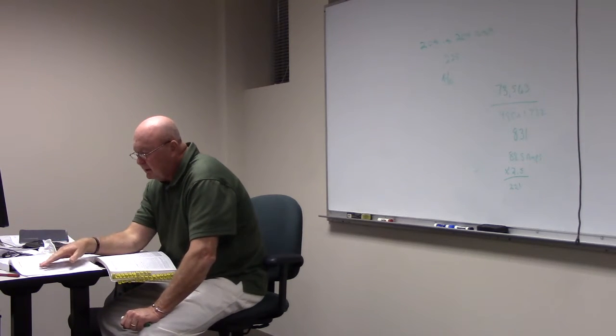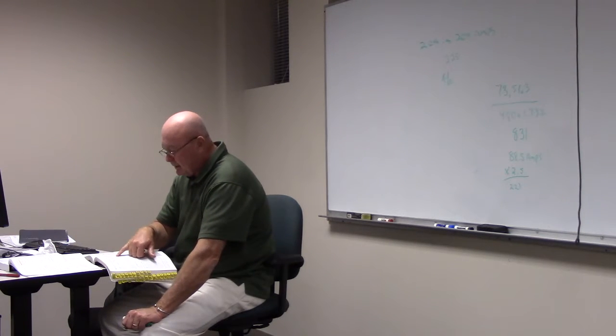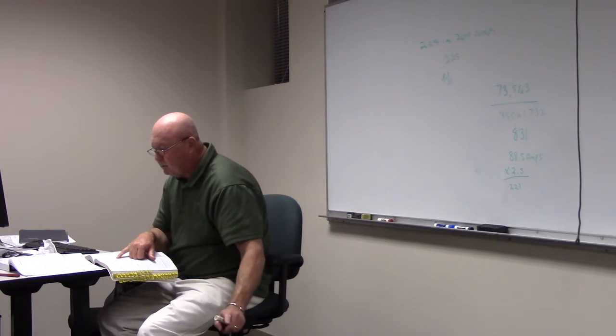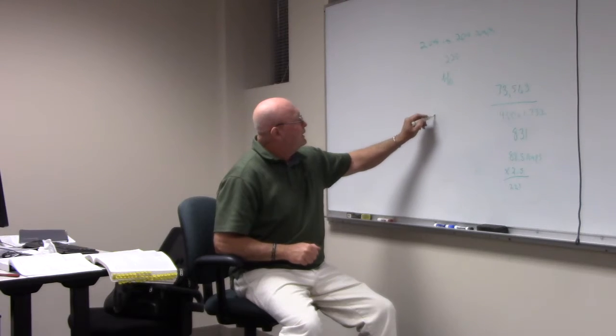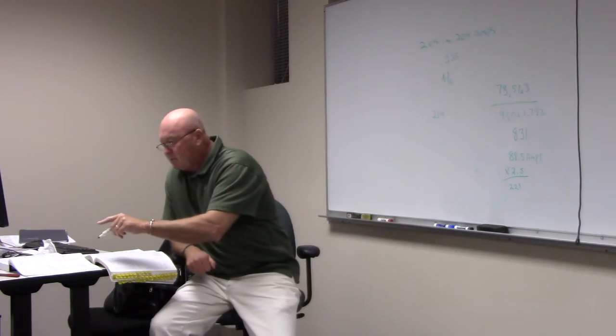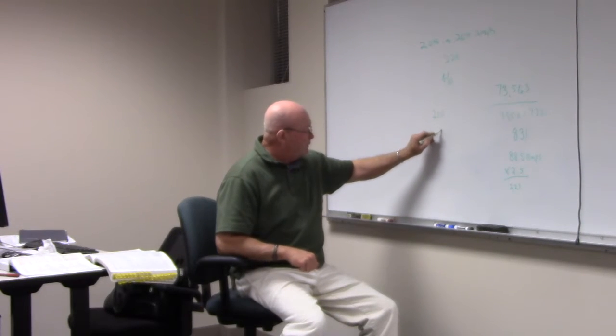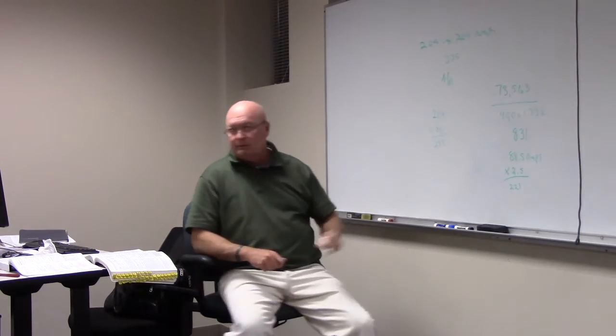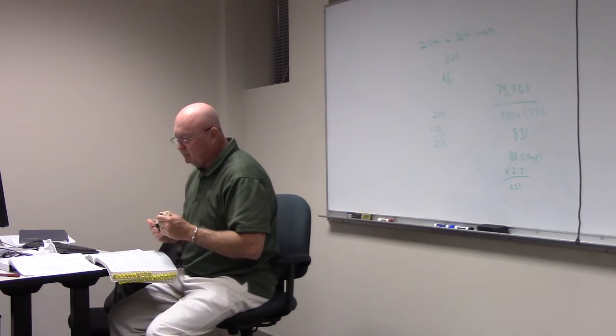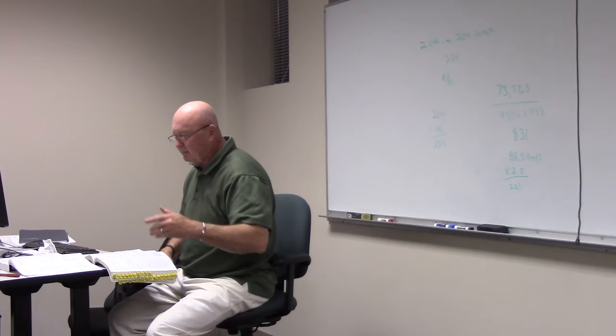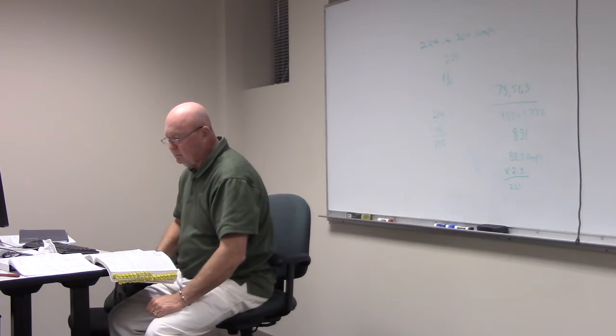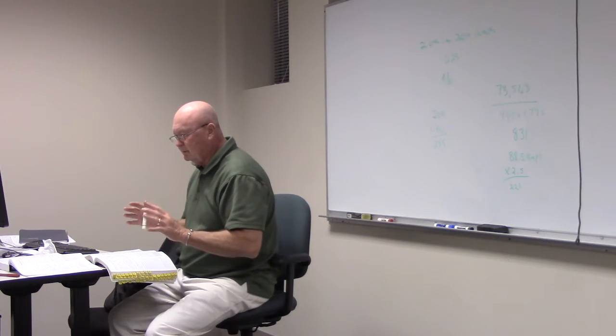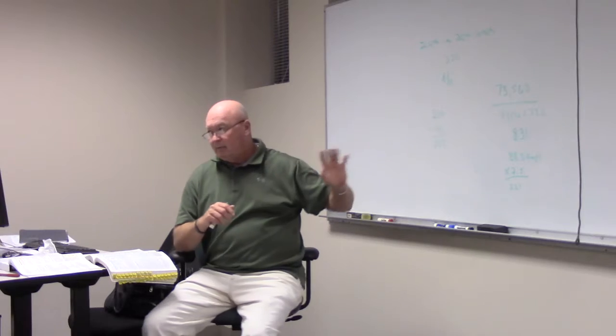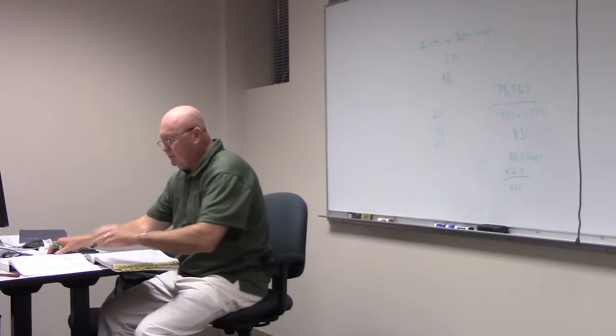So if you look at what we did, and we see in our book, it says 221 amps. That is, it may not exceed this rating. The secondary protective device is 125%. We get that from that same table. So we go back to what we had earlier, because we had that 204 amps. And you see the maximum you could actually do would be 1.25, which is 255. For that table, that's the maximum. So the largest permissible standard overcurrent device would be 250 amps. But we're back to where we were a minute ago. Let's not worry about that, I'm just showing you that.